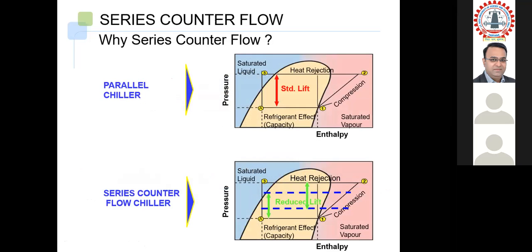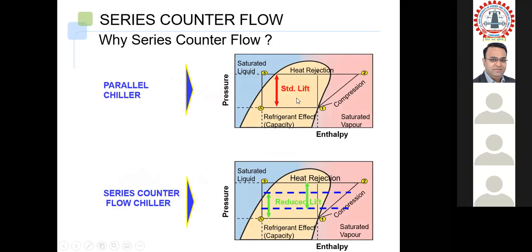So what is the benefit? Before we get into that, why series counterflow? Some of us from the mechanical batch have already seen this pH diagram. The performance of a chiller depends on the refrigerant effect and the heat rejection. The pressure difference between these two is what determines the compression work. If we are able to reduce this, we call it lift in our terminology. The higher the lift, the more the power consumption. The lower the lift, the less the power consumption.